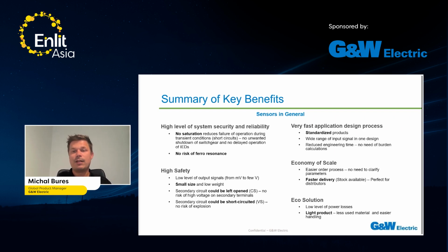Very fast, let's say, design process. So it is standardized, as I mentioned. The standard describes what the output voltage should be and what the burden should be. So one design can cover a wide range of applications. Also, there is the economy of scale. It is much easier to order the sensor than the conventional CT/VT, so you don't need to clarify parameters like the burden or the output. It is already standardized and works perfectly with IED.